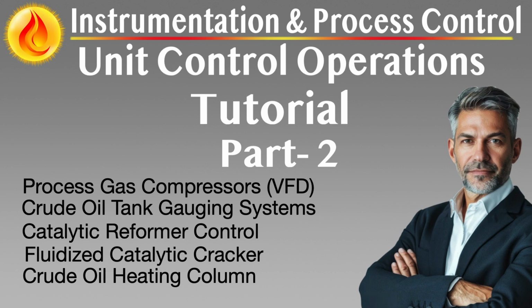Safety and trip logic in VFD-controlled compressors are now more sophisticated. Control systems are integrated with safety instrumented systems (SIS) and emergency shutdown systems (ESD), enabling tiered responses based on alarm severity. For example, high suction pressure may trigger controlled deceleration, while critical low flow near surge limit can trigger a bypass valve in parallel. Soft shutdown logic protects both process continuity and equipment, reducing risk during utilities failure, load shedding, or unit shutdowns.